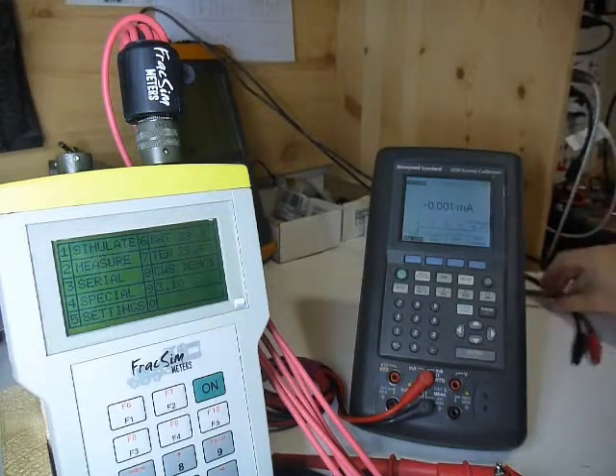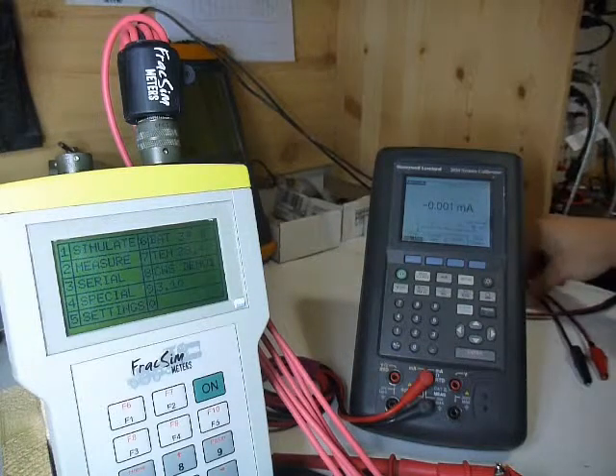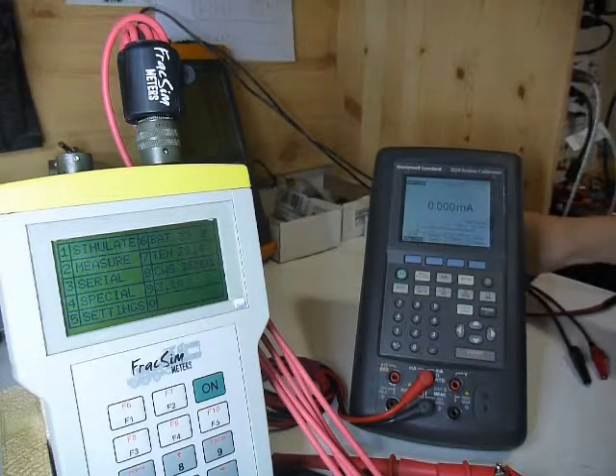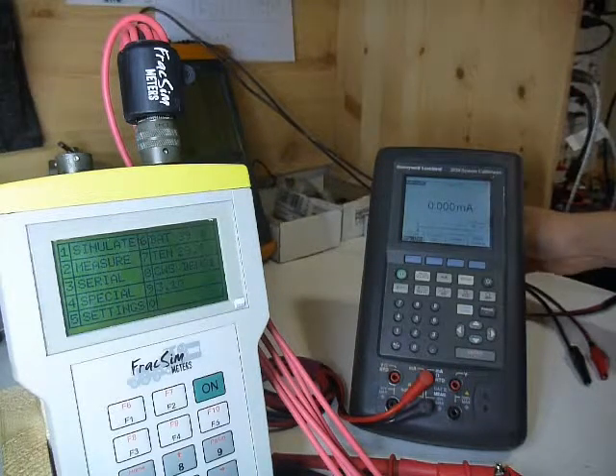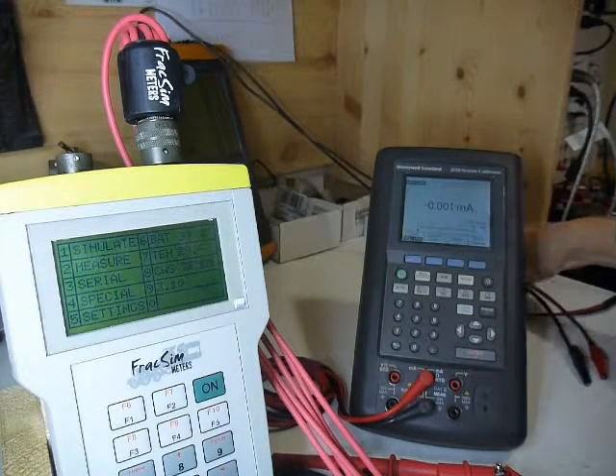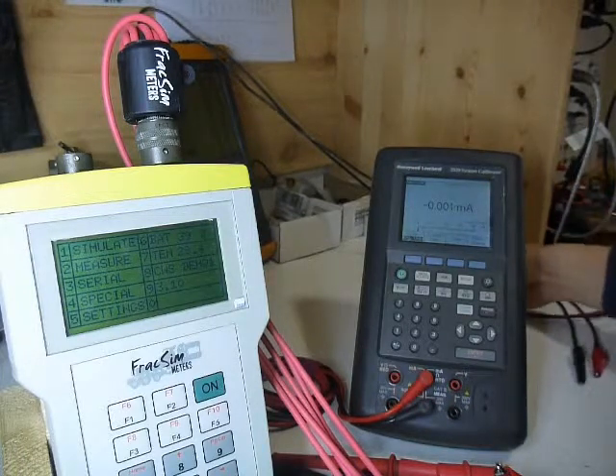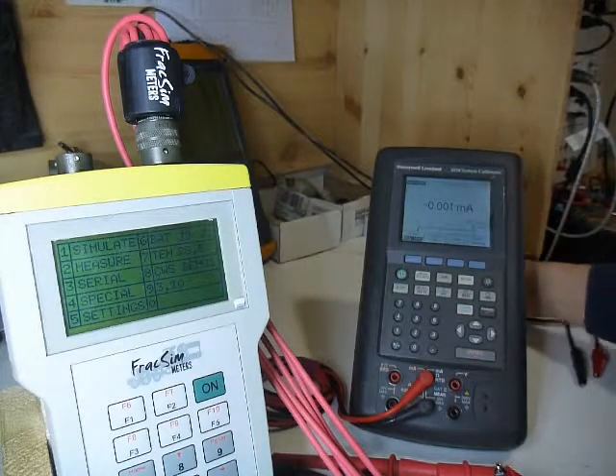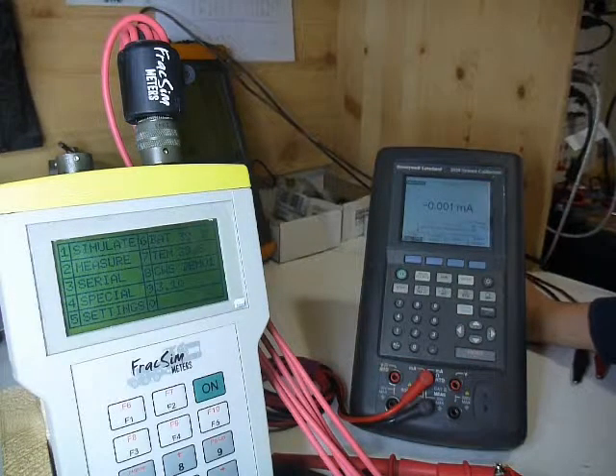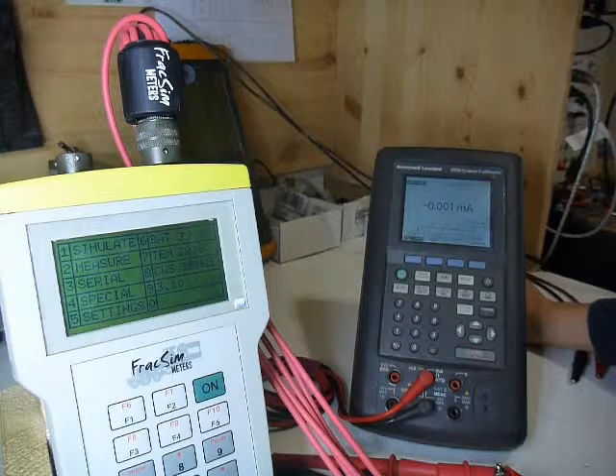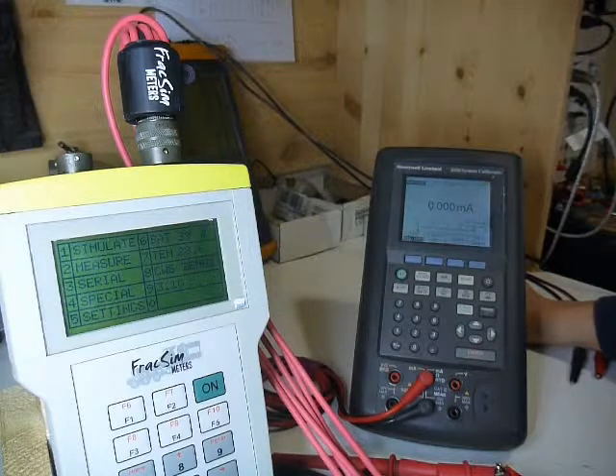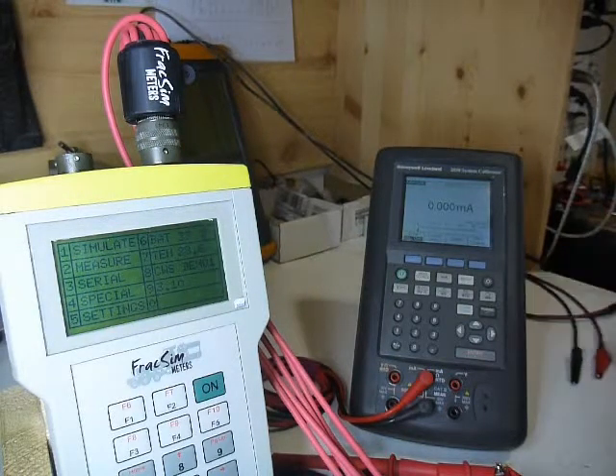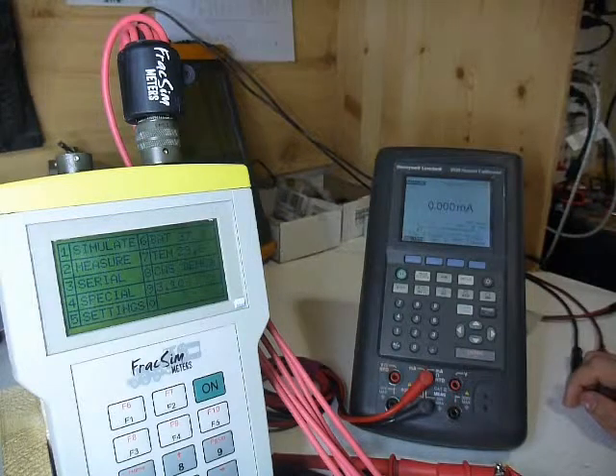In terms of how you apply that to a unit, if you were to consider a frac pumper and you wanted to simulate a pressure into the frac pumper and you wanted to use the electric power from the frac pump system, you would use the sinking, not the sourcing. Now, in some applications you could source current into a frac pumper, but you would not be troubleshooting the whole circuit. Most of the time you would actually be sinking current. So anyways, we'll go over sourcing current first because it's the easiest.